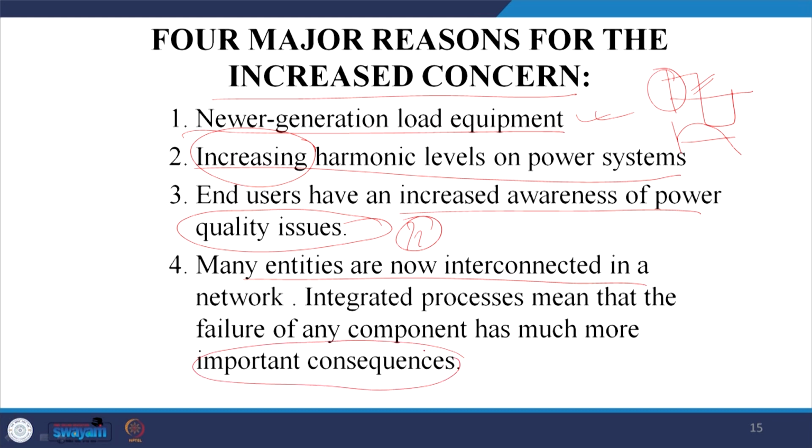For example, it happened to our institute a few days ago that there was a power cut because the feeder was bad, but solar was generating power and ultimately we failed to evacuate that power because of lack of power supply. For this reason we are required to stop the solar inverters.